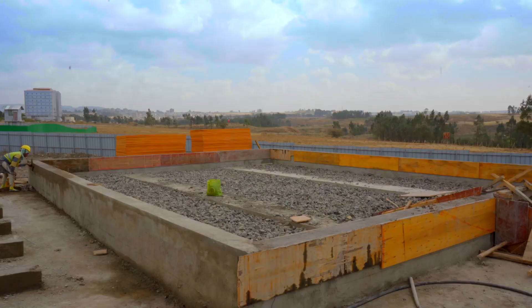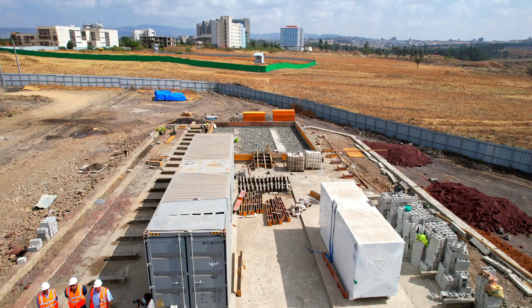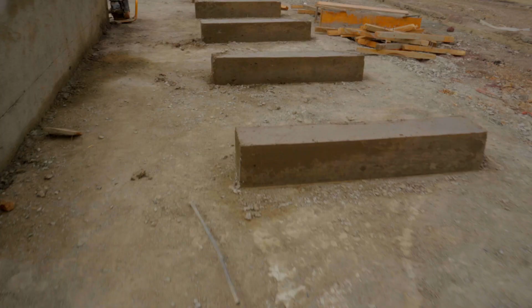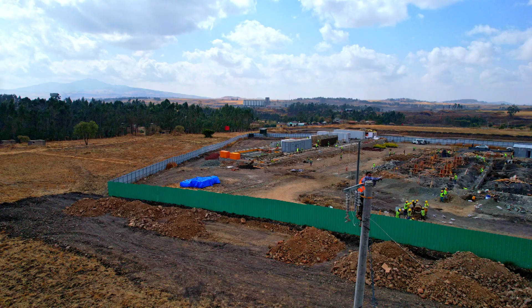Over in this section we have space for our 2 diesel tanks, 2 by 23,000 litre tanks, which provide enough diesel for 24-hour operation for 30 days continuous without a refill. Over here we run all our cable infrastructure, a full A-B redundant system, so we can always lose one leg without losing power to our facility.